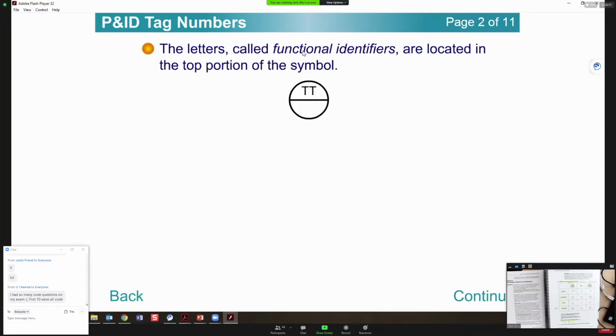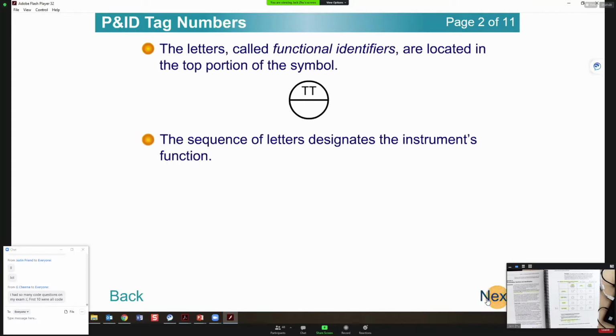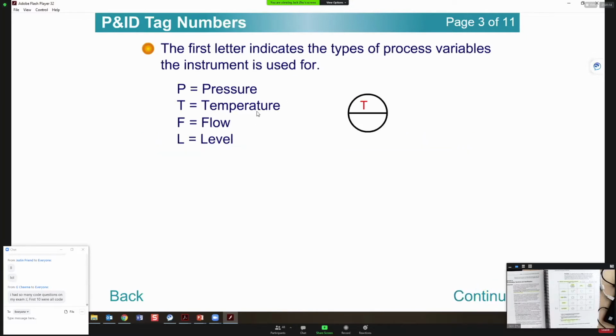The letters, called the function identifier, are located on the top portion of the symbol. So the top uses letters to identify the function. The sequence of the letters tells you the instrument function. The first letter usually tells you what type of process variable the instrument is for. You can use pressure, temperature, flow, level. That's in Appendix B. That's the identification letters.